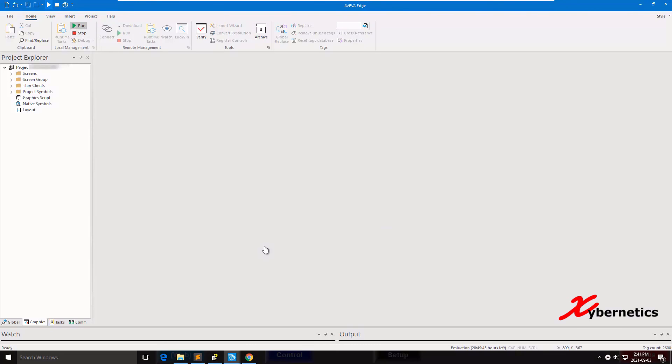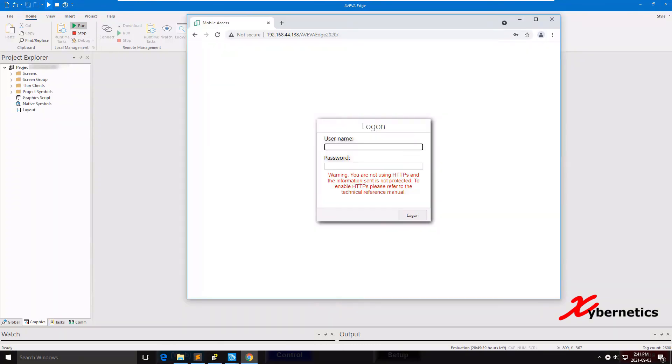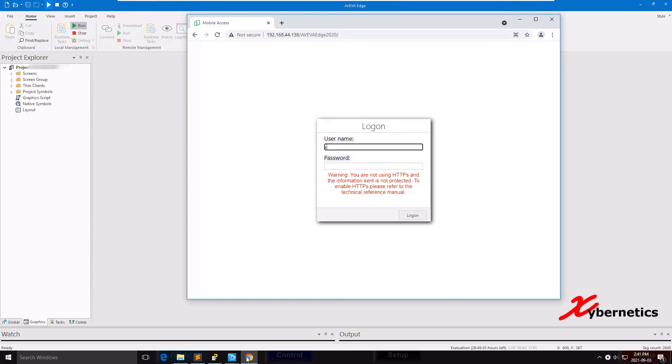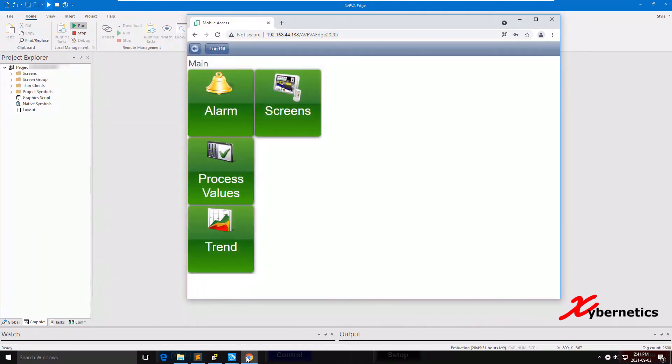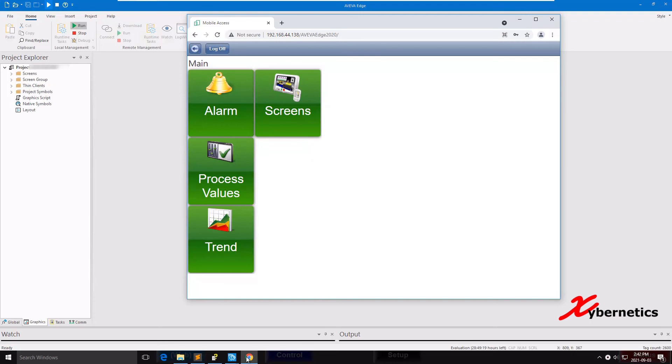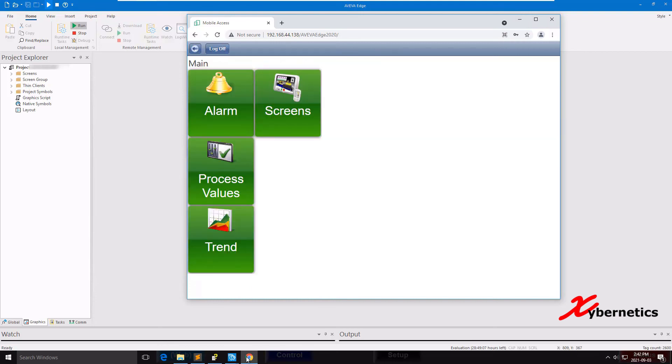If you get this error message, go back to your Studio and try running it. Once your AVEVA Edge is started, go back to your browser, hit F5 to refresh, and enter your username and password again and hit Enter. This time around you'll be presented with a bunch of selections and menus. They are mostly all blank. Process Value is blank, Screen is blank too. The reason for that is you haven't set up the mobile access screens yet.